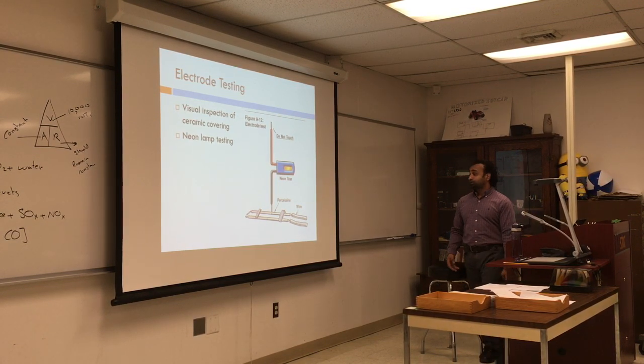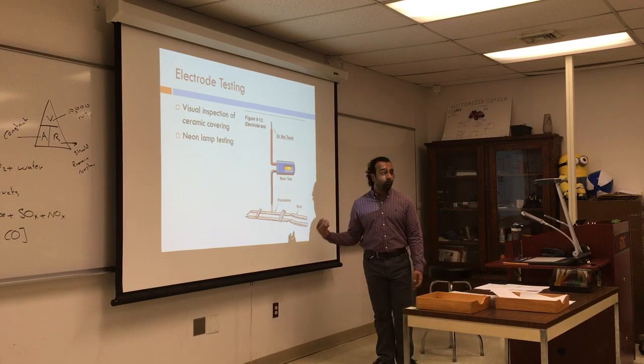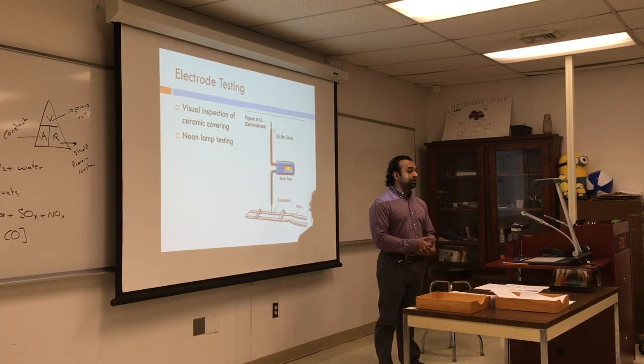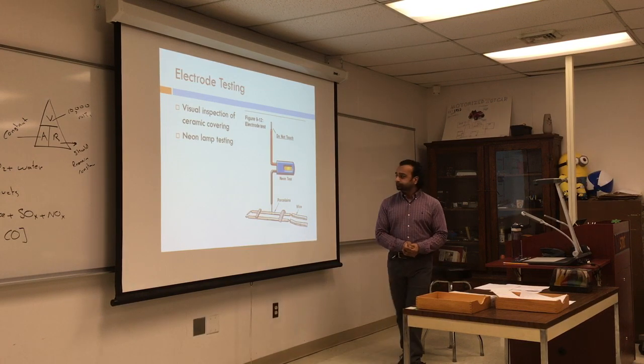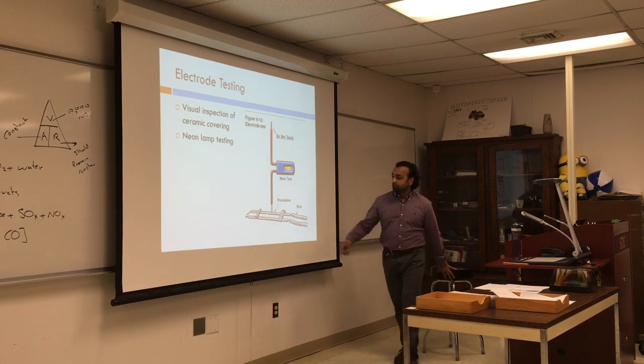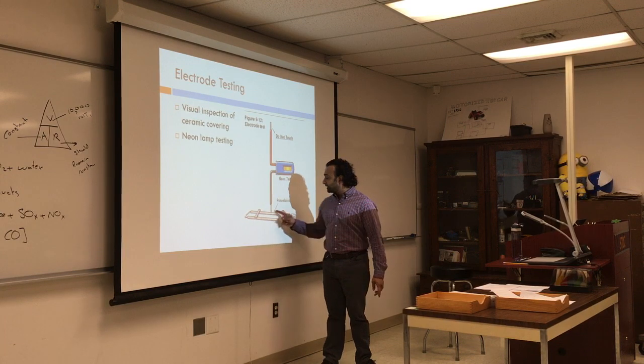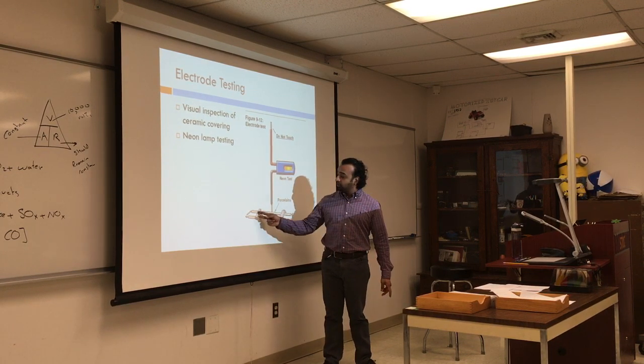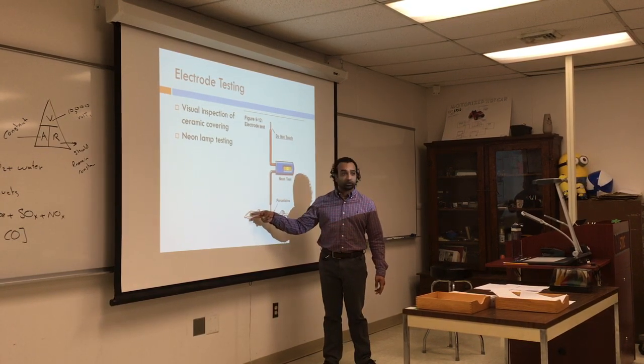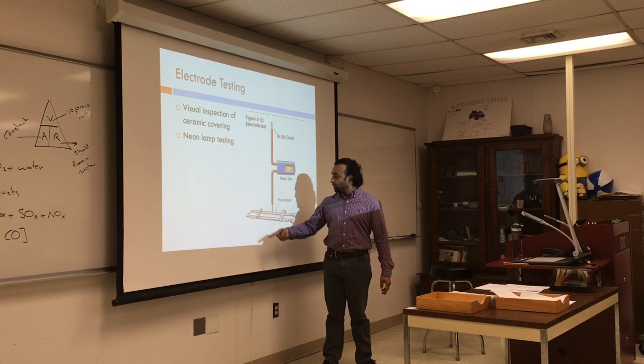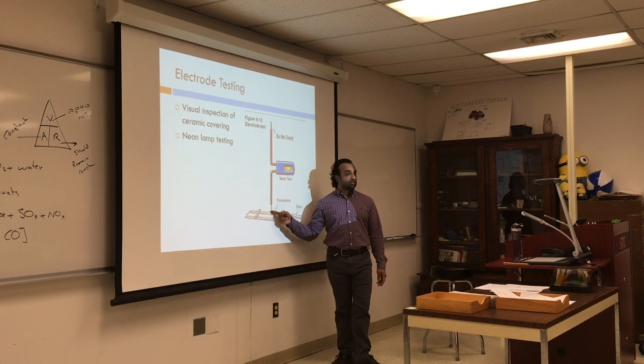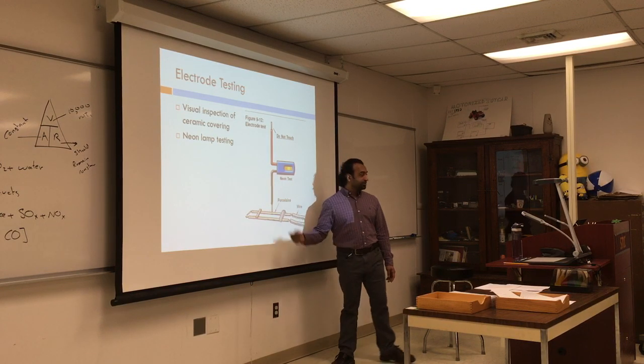And when in doubt, what I usually do is take the whole burner out, turn the ignition on, and look for the spark and see if it's there or not. A lot of times those gaps wear out, or you get voltage all the way through the bus bars, but it does not make it all the way to the end. Or sometimes the holders are conducting the voltage through the casing.